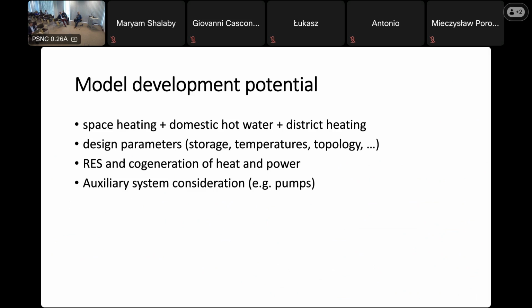Also, when we connect to district heating, there are different temperatures in the heating system, but also different pressures — something we didn't talk about today. Sometimes there's a need for quite big pumps if we connect to district heating with the data center cooling system, and these pumps, needed to keep the pressure, could represent a big share of energy in such systems, so this should also be considered.